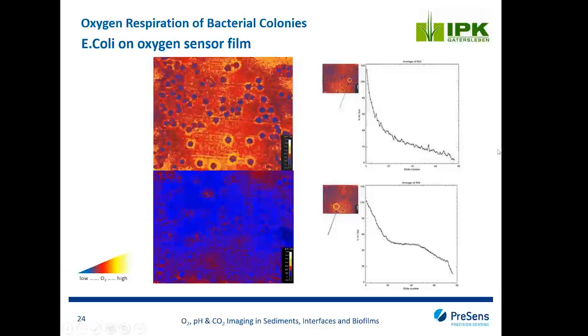Rob, there's a question concerning this application. How is it about sterilization of the sensor foils with the E. coli measurement? The oxygen sensor foils may be sterilized with 70% ethanol, or you can also use ethylene oxide or gamma irradiation. In most cases, 1 minute of plasma treatment is also feasible. And there is a question about the calibration. Is the system pre-calibrated? Actually, the system is not pre-calibrated, but for example, with the oxygen sensors, you just need to do a 2-point calibration and then you can get your oxygen values.